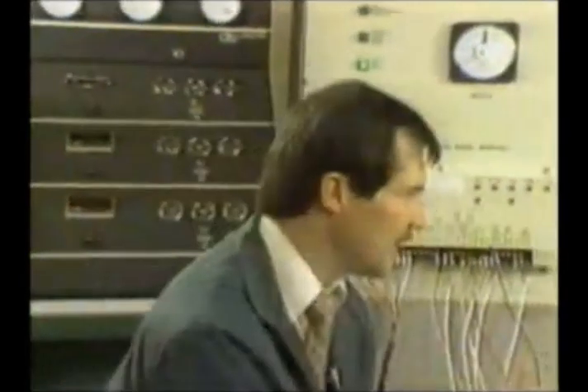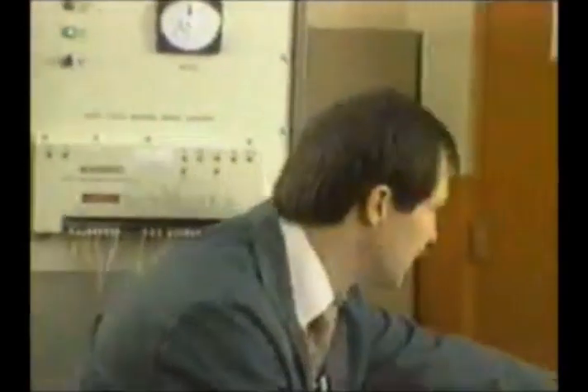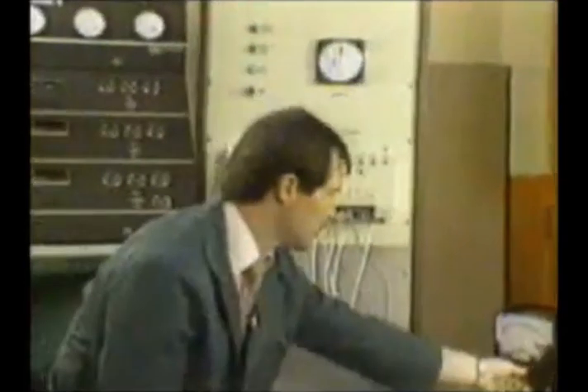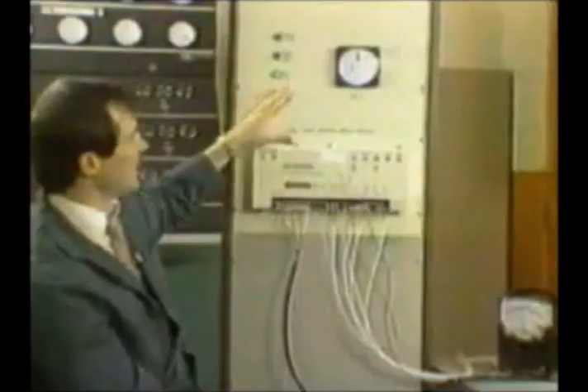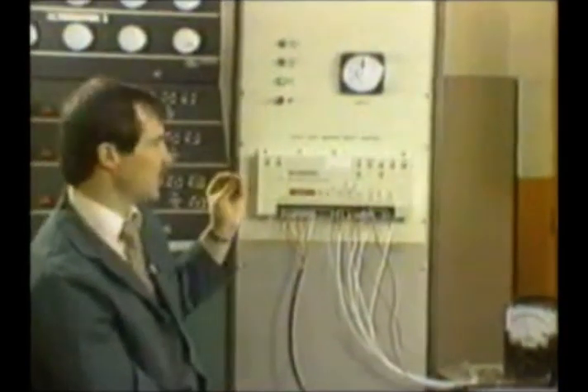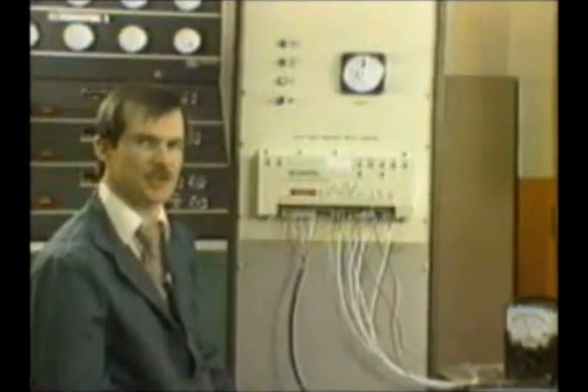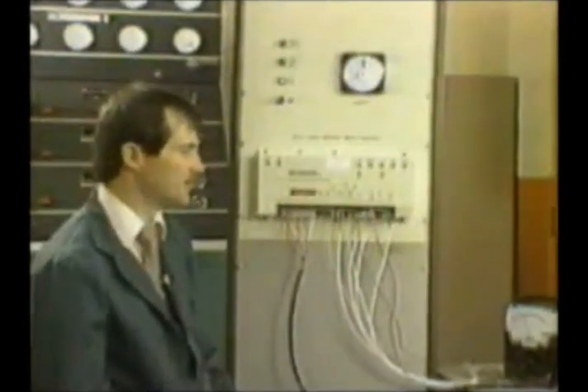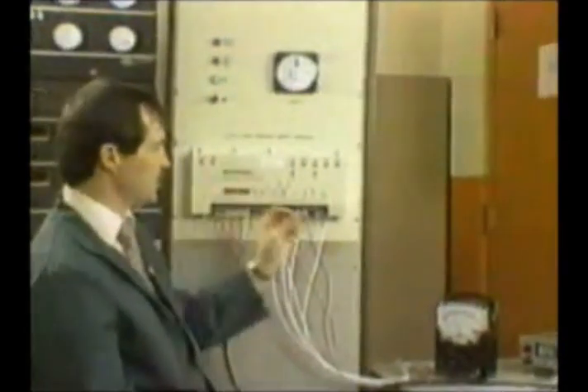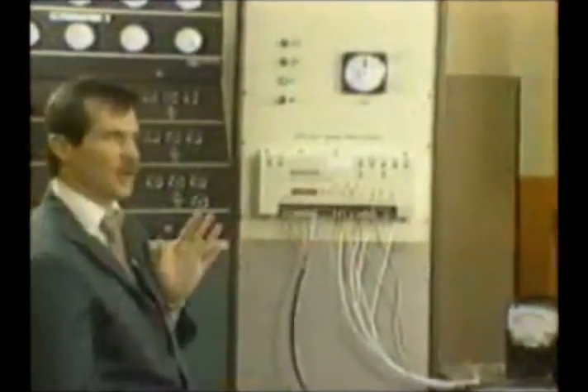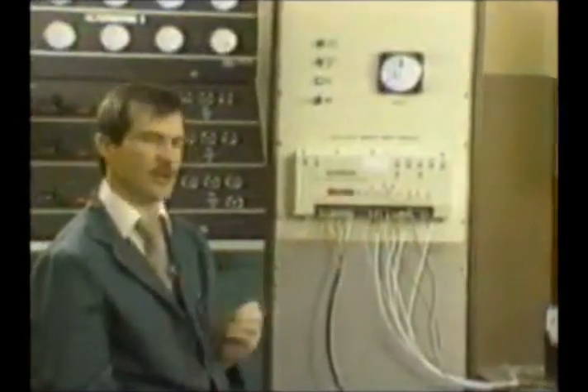Now that you're up and running, let me go ahead and load the engine. Turn my analog meter up. You can see we stay running at 60 hertz. That start fuel limit is out of the picture completely now. So now we're running at 60 hertz. Let me go ahead and unload the unit. Now I want to point out droop and load gain.